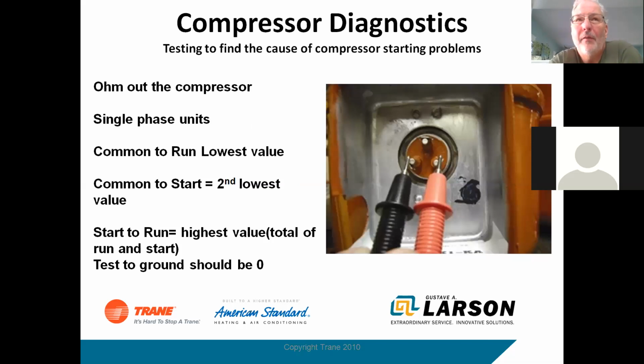Okay, so if we've checked out the voltage side and we see everything's okay and we still have a compressor that's giving us problems, next thing you want to do is ohm out the compressor. Now, I realize getting to the compressor isn't always the easiest on some of these units. So if you can disconnect the wire back at the contactor, and I've got some slides later on to show how to grab those readings, you can do an ohm reading or a ground reading through the harness that goes to the contactor. Just make sure that you disconnect the wires, okay?